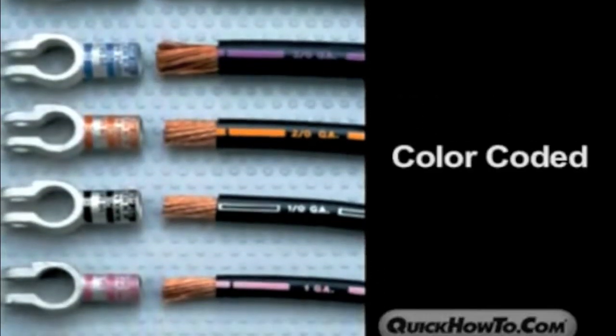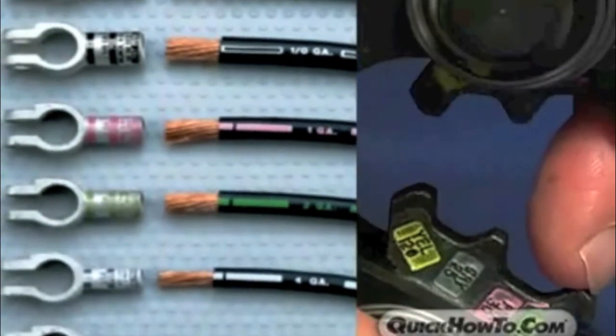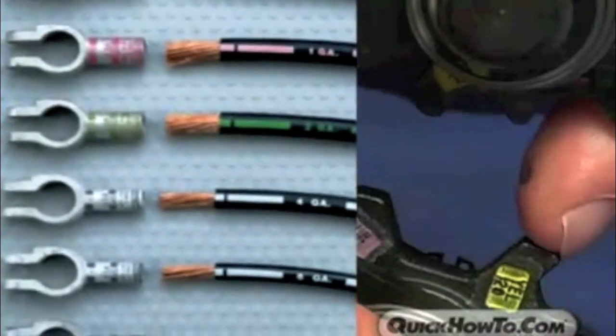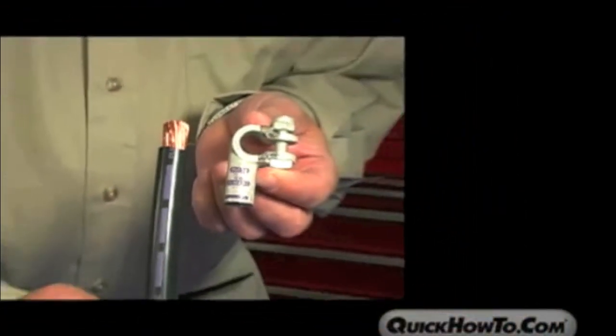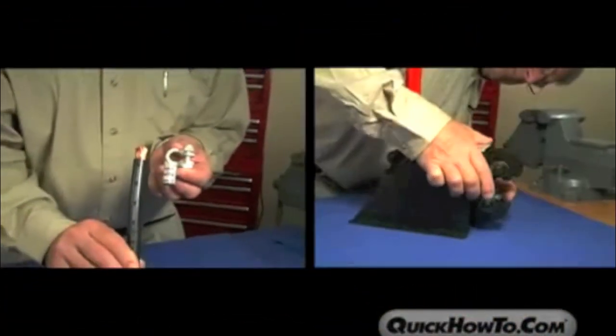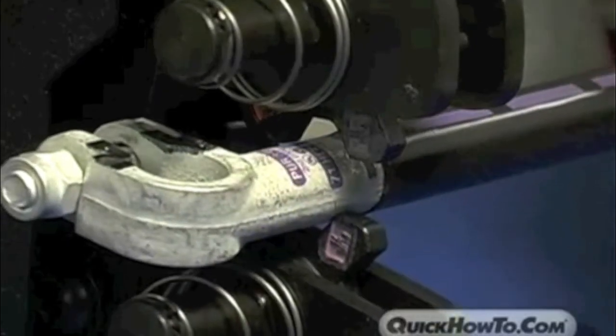Another unique feature is that Quick Cable's battery cable is color-coded to match the appropriate connector and die setting of the hex crimp crimper. For example, a 3-aught gauge cable has a purple color strip that will match the purple lettering on the 3-aught gauge Quick Connector and the purple setting on the hex crimp crimper.